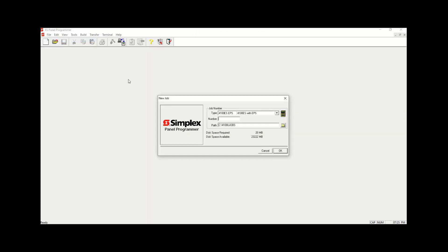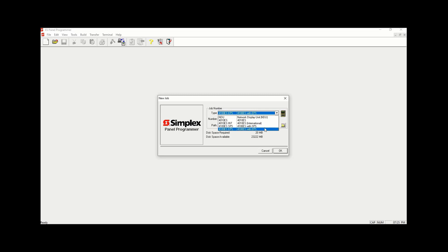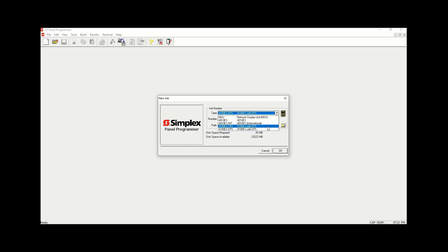Without further ado, we're going to click File > New. We have two options: 4100ES with SPS, which is a System Power Supply, and 4100ES with EPS, which is Expansion Power Supply. The difference is that SPS is designed to work with all conventional horns, strobes, and horn strobes, while EPS is designed for addressable horns, strobes, and horn strobes. In our case we're going to use SPS and provide a general name.